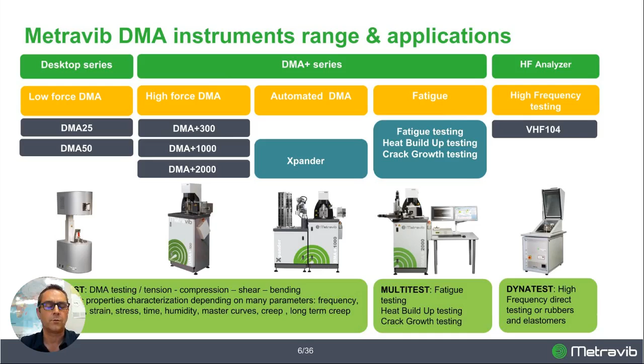And at last, the VHF 104, which is a very unique product focused on the high frequency testing, direct high frequency testing, and making possible to address direct measurement up to 10 kilohertz, while, let's say, traditional DMA stop around practically, theoretically 100 hertz, but practically 50 hertz for most of the traditional DMA, except for the DMA+ Metravib, where we can reach 1 kilohertz in some configuration. The VHF is a very unique instrument to address a very high frequency range for rubber materials.